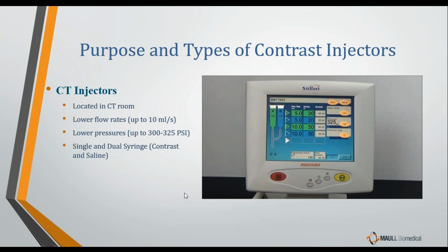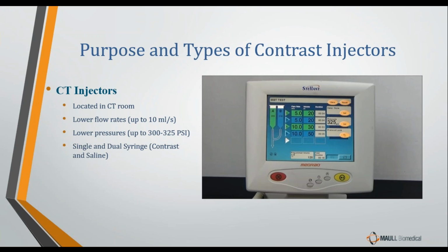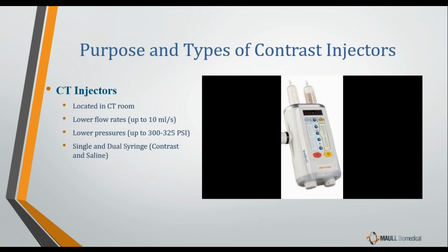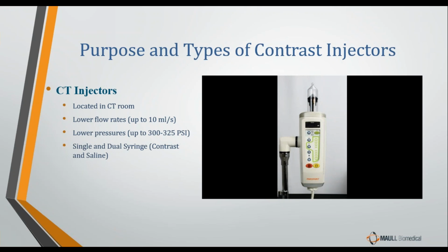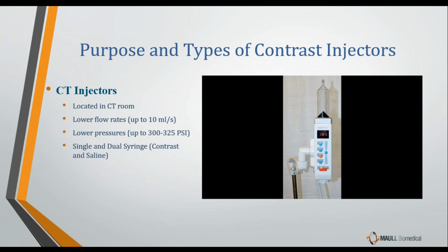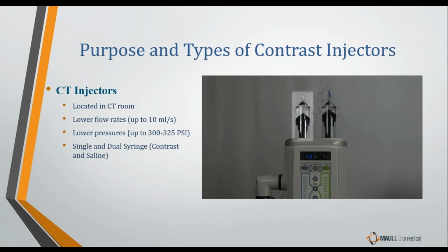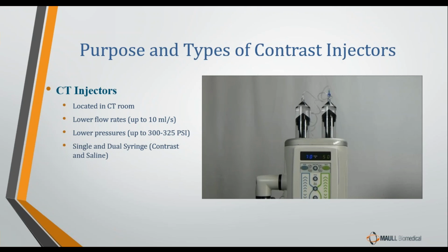Now, because these CT injectors are only capable of flow rates of 10 milliliters per second, they are considered relatively low pressure injectors. In this case, the CT injector can only go up to a pressure of 325 psi. Now, CT injectors come in both dual and single syringe configurations. Some CT injectors just have the one syringe, and it's full of contrast, obviously. Some CT injectors are dual syringe injectors, meaning one syringe has contrast in it, the other syringe has saline in it.